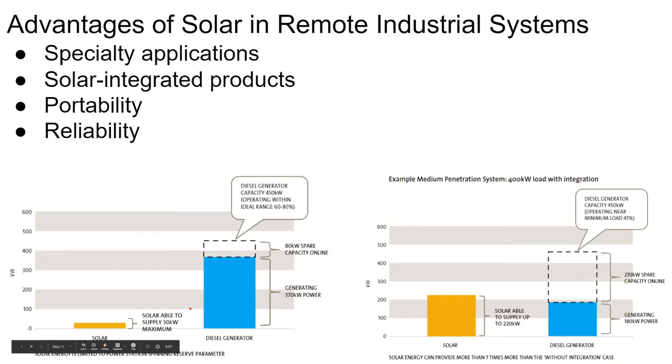Similarly, a small solar array can be successfully AC coupled to on-site gas generators, provided that it is very small compared to the overall operating capacity of that generator. Monitoring the site electric data can be a good starting point as well, so collecting that data is important. This is actually pretty interesting, because what that means is almost like a very simple residential solar array, where it's just one inverter, the modules are put up on the roof, and it's just connected to the grid and backfeeding the grid. A very similar simple solar array could be added to an off-grid diesel camp without disrupting any business as usual. At that point, the solar array would be generating at the cost of the diesel fuel.